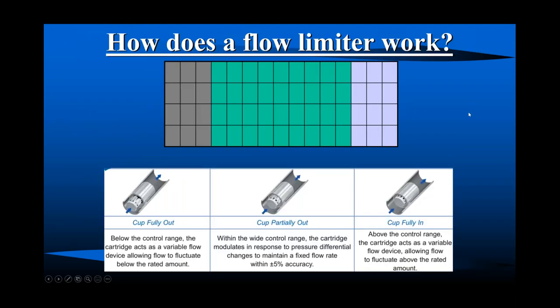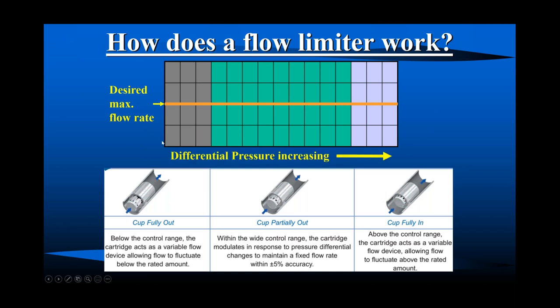So how does this thing do its job? How does a flow limiter work? So we did our calculation. We have our design day flow through our terminal unit. That is our maximum design day flow right across this orange line here. And the flow across this device will increase as differential pressure increases across it. So the more pressure across that, the more what's going to happen across that flow limiter's cartridge? It's going to look like that. That's kind of the profile of what it looks like.